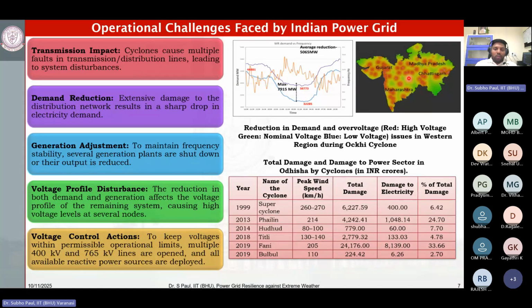That over voltage is very high, not within the permissible limit of our power grid. So at that time voltage control actions have to be taken, like turning on reactive power absorbers, such as inductors, to absorb more reactive power, or turning on dump loads for load and generation balancing. But these are costly solutions, because you're generating from the thermal power plant and wasting that energy on a dump load.